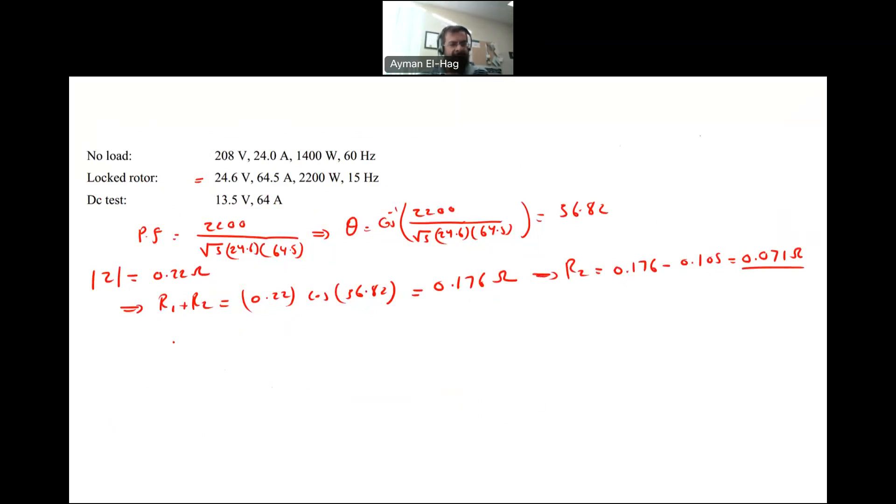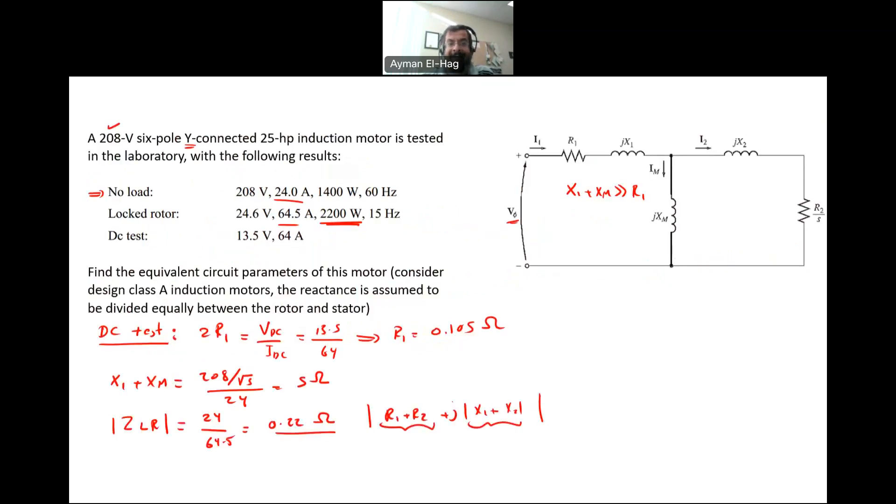Now let's find X1 plus X2, which equals 0.22 sine 36.82. This gives me a total value equal to 0.132 ohms. Now this reactance 0.132 is done at 15 hertz. The locked rotor test, we do it at a reduced frequency.